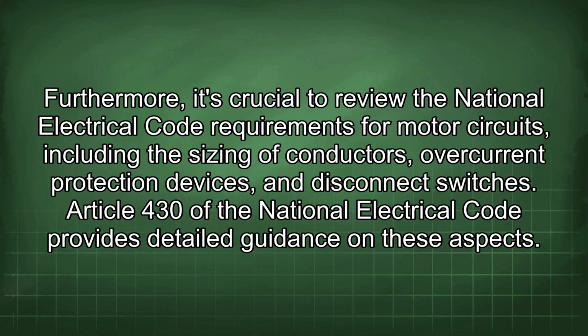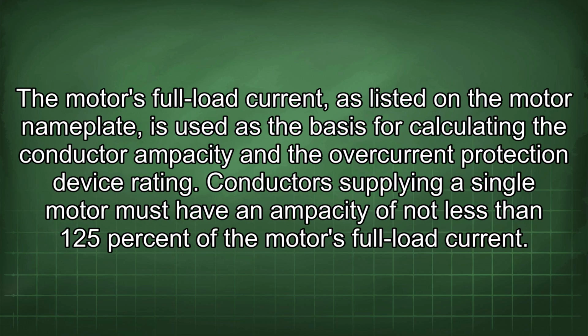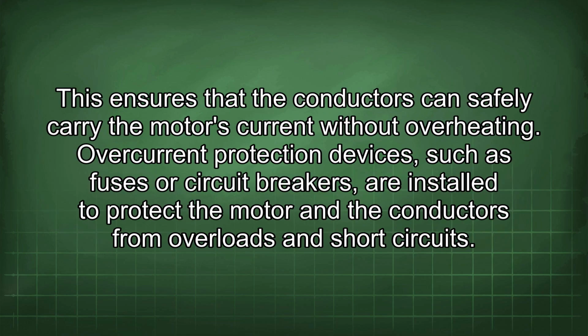Furthermore, it's crucial to review the National Electrical Code requirements for motor circuits, including the sizing of conductors, overcurrent protection devices, and disconnect switches. Article 430 of the National Electrical Code provides detailed guidance on these aspects. The motor's full load current, as listed in the motor nameplate, is used as the basis for calculating the conductor ampacity and the overcurrent protection device rating. Conductors supplying a single motor must have an ampacity of not less than 125% of the motor's full load current. This ensures that the conductors can safely carry the motor's current without overheating.